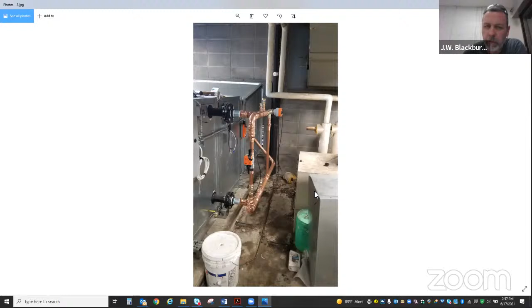Yes sir. Now do these UV lights go on after it goes through the filtration system, or what's the exact supply side spot? The idea, if I recall, is it should be closer to the coil in order to keep that coil clean. So it would be on the leaving side of the filter. Once we get those units set, we only have one more left to set, and then we'll get those UVs installed. So post filter and pre coil. Yes sir, perfect.